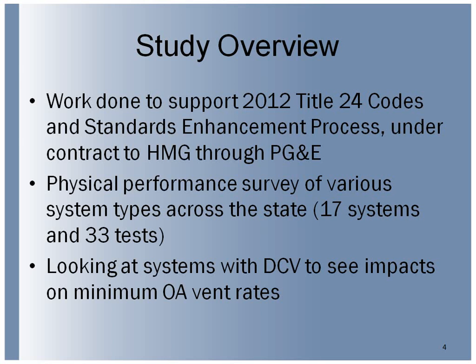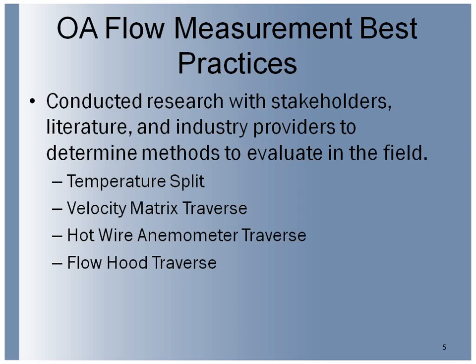This work was done as an offshoot of some of the non-residential codes and standards enhancement work we were doing with PG&E, and included a pretty rigorous physical performance survey in the field, all over the state, different systems that we could get access to, 33 tests in total. We were originally looking at demand control ventilation systems to see what the impact of having demand control ventilation was on minimum ventilation rate performance, but it morphed into something different based on the data we found.